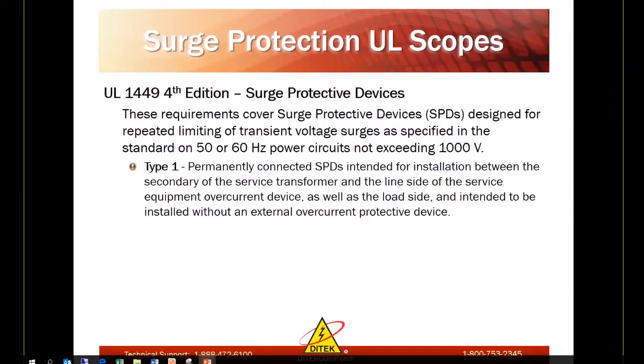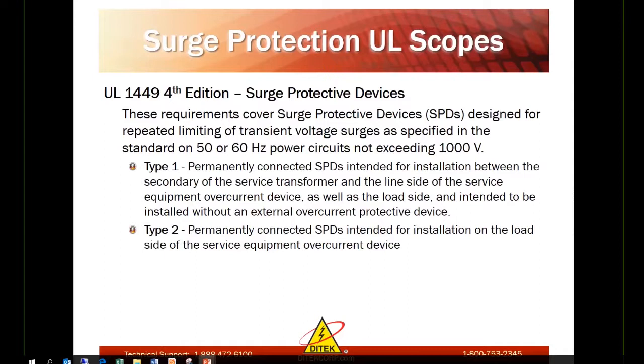There are three classifications. There's a Type 1. This is line side protection. This is a permanently connected SPD, surge protection device, intended for installation between the secondary of the service transformer and the line side of the service equipment overcurrent device, as well as the load side. So a Type 1 can be used line or load, and it's intended to be installed without any external overcurrent device. Type 2 is a load side protector. So it's a permanently connected SPD on the load side of the service equipment overcurrent device or a circuit breaker.